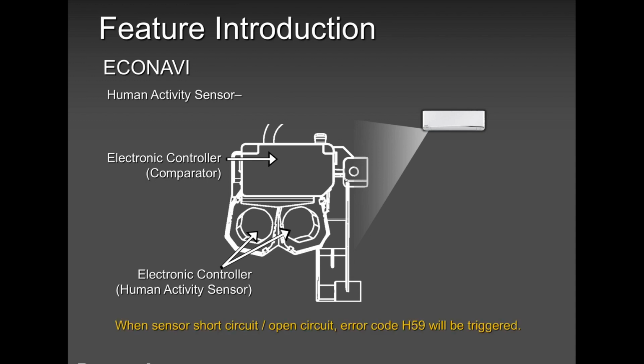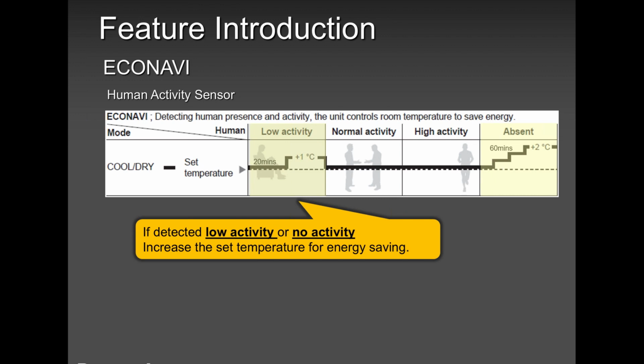So what it does, the electronic controller, the comparator, it has the sensor there. It checks on you all the time. It's not a camera, guys. Okay, don't worry, it's not a camera. It just picks up on temperature. And as I mentioned, when you are absent, it goes 2 degrees higher or 2 degrees lower, depending on which mode you are in. Okay, if you're in cool mode, it will go 2 degrees higher. If you're in heat mode, it will go 2 degrees lower. Then when you show up again and activity kicks in, it can catch up quickly and give you the comfort you need right away, almost right away.